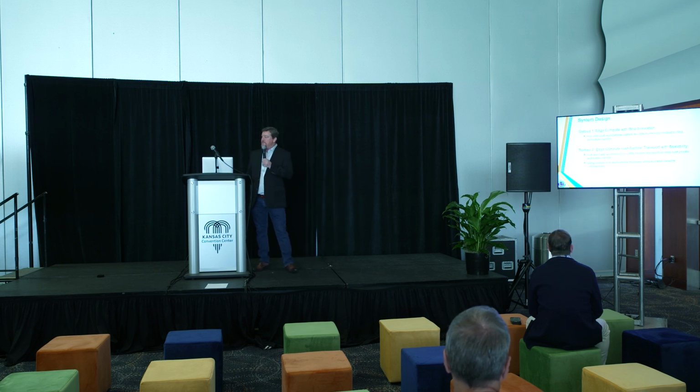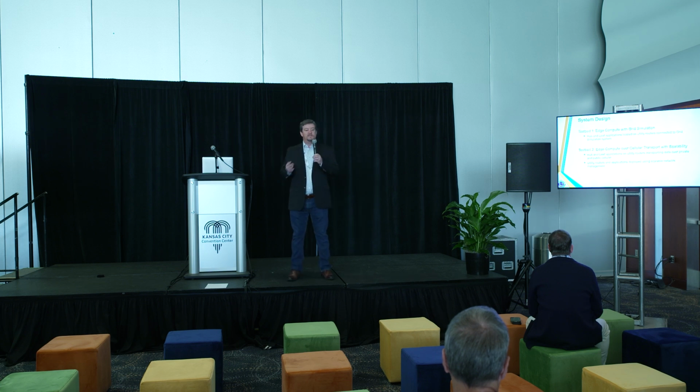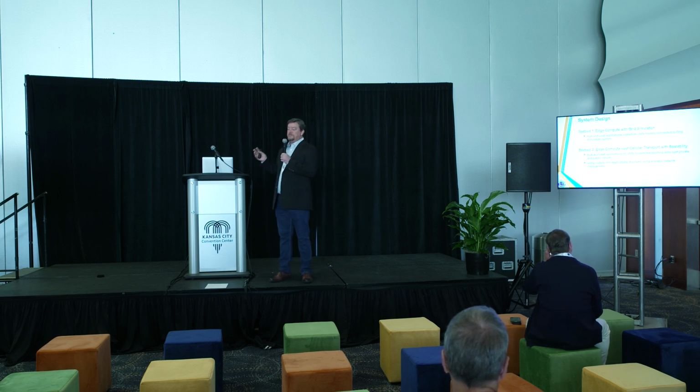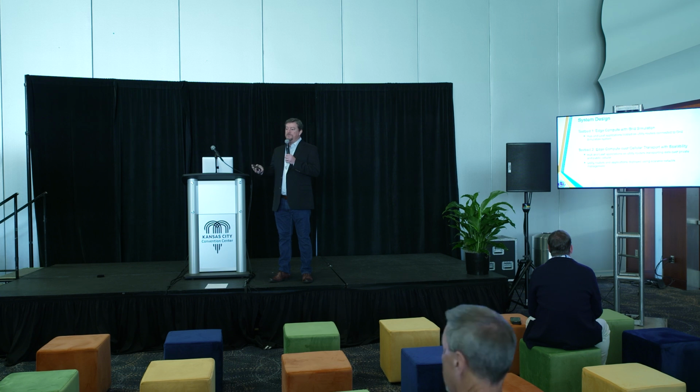So the 2 test beds that we're going to talk through, the first is in line with a real-time hardware-in-the-loop grid simulator. It's made by Typhoon. So that simulates grid states on feeders. That grid simulator was connected to those controllers, the cap bank controller, voltage regulator controller, and the battery energy storage controller, which were then connected to our routers, the Cisco routers hosting Eaton applications. And that's the first test bed. So we're going to walk you through those results.